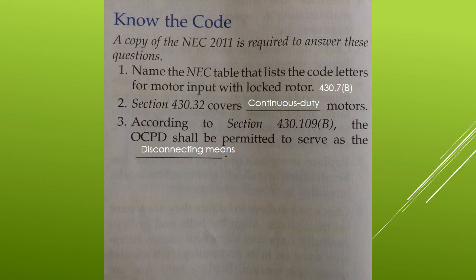Moving on to the Know the Code section. Name the NEC table that lists the code letters for motor input with locked rotor. That would be table 430.7(B). Question 2, section 430.32 covers continuous duty motors. Question 3, according to section 430.109(B), the OCPD shall be permitted to serve as the disconnecting means.